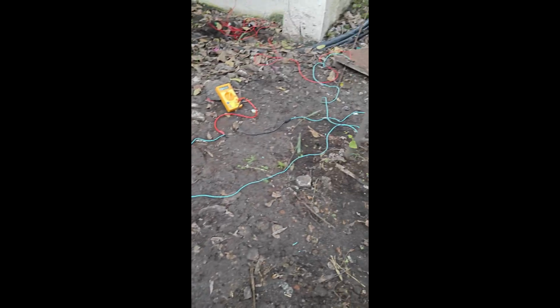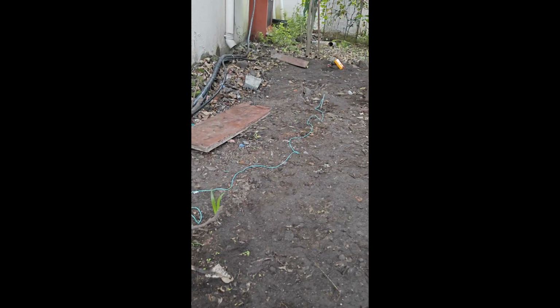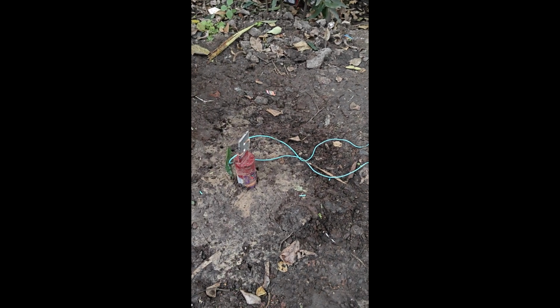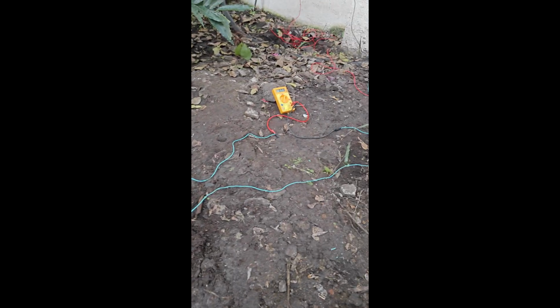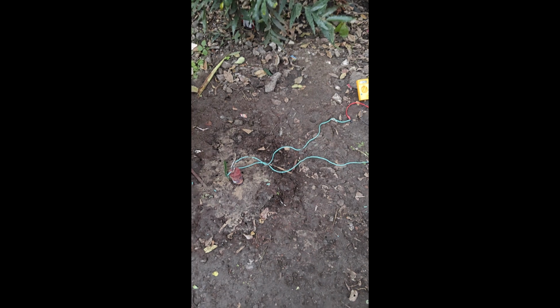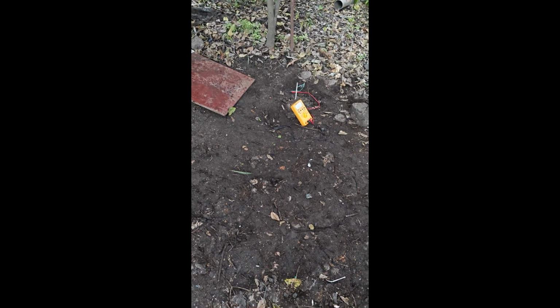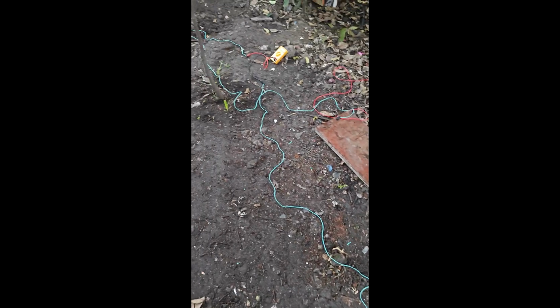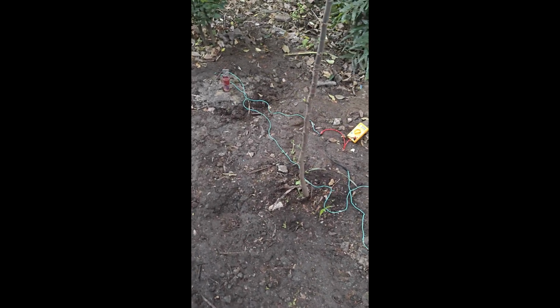In our project, we have measured the earth resistance value, and we are also continuously measuring the deviation of the earth pit resistance. So we are using the fall of potential method here, and we have practically implemented it. We are taking the readings of voltage, and also the reading of current flowing in this circuit, in which we have implemented the fall of potential method.